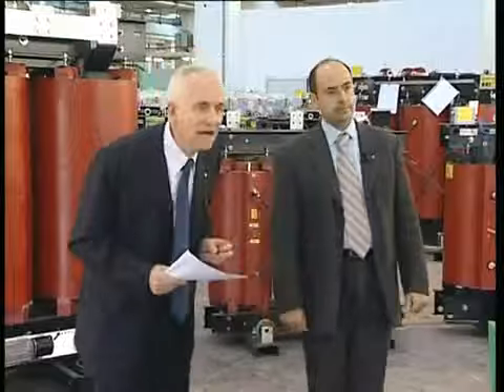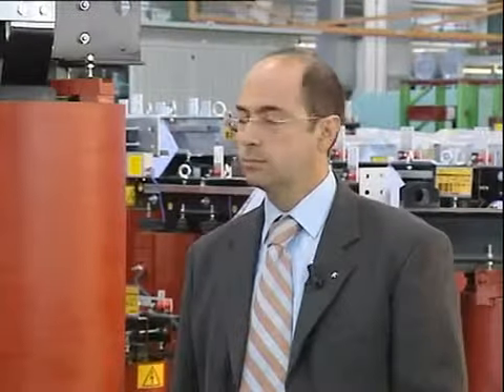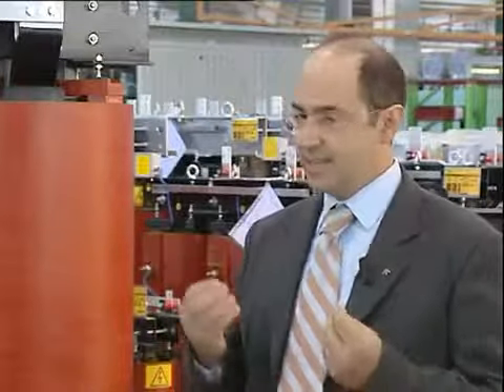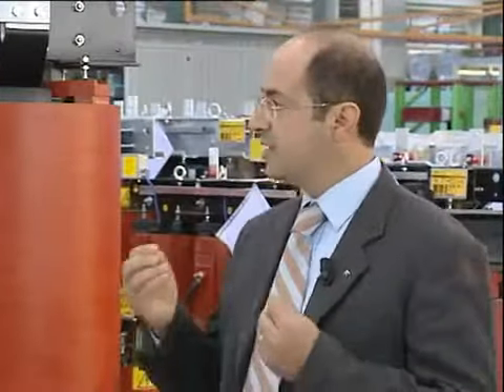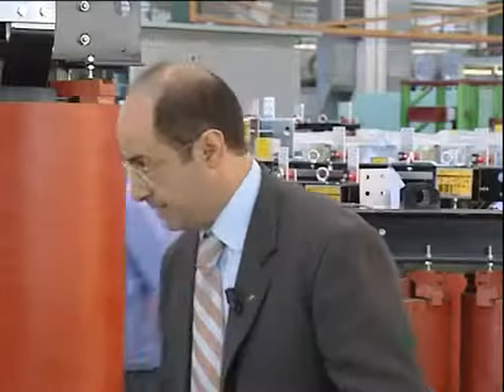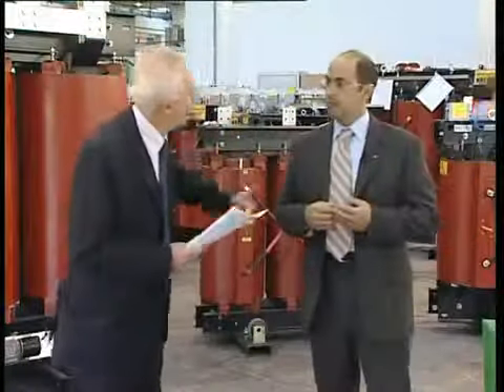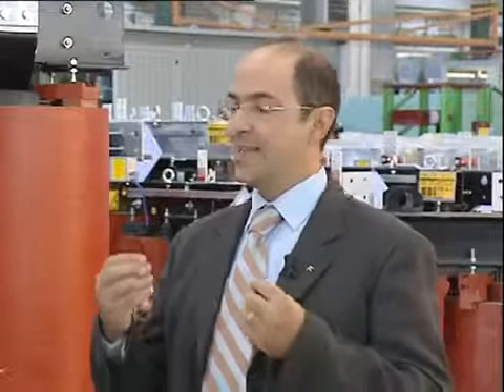Good. Since we are talking about quality, I would like to ask Mr. Marini a specific question. What are the particular features characterizing the quality of a resin-insulated low-medium voltage transformer, and what is EDM's position in this respect? First of all, reliability. This means that the transformer must be sized so as not to stress the insulating materials, neither from a dielectric standpoint nor from a thermal one. Is this aimed at increasing the transformer's life? Certainly, because a transformer's life is related to its insulating materials. The better their relative size and their operating conditions, the longer the transformer's life will be.